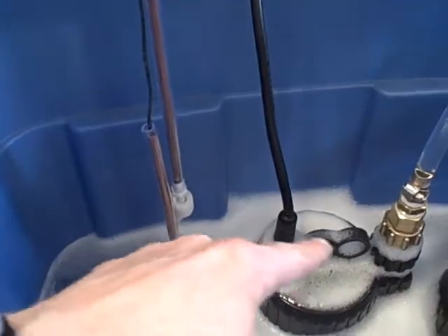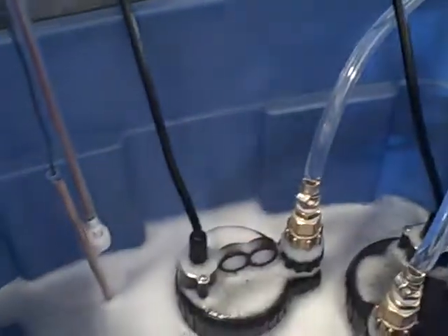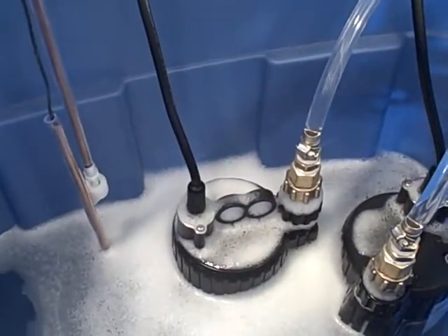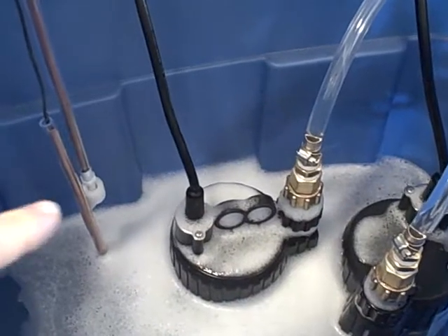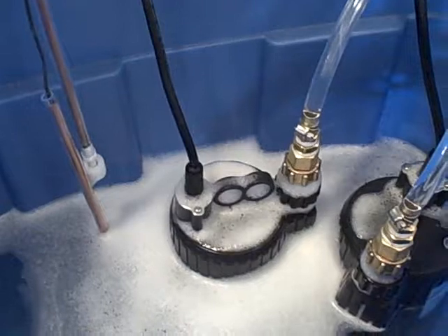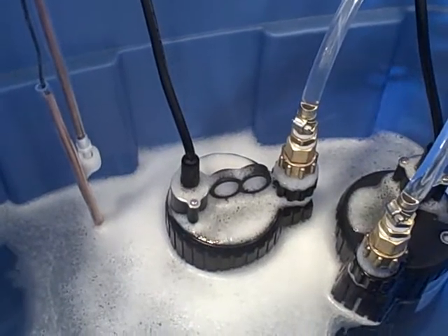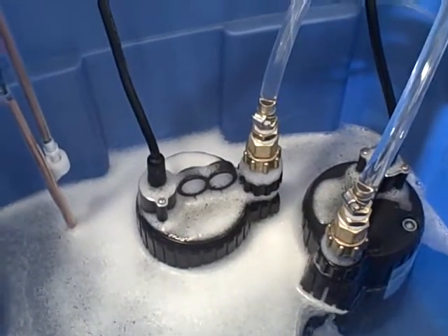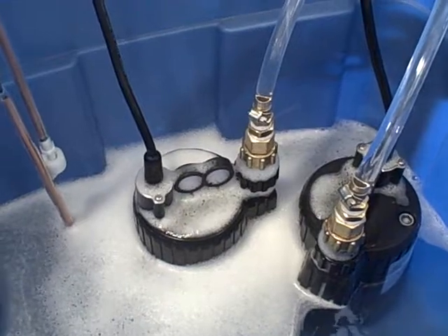When the wastewater reaches the high level switch, it turns on a pump, and that pump then pumps to the wastewater treatment plant. The pump continues to run until the wastewater gets down to the low level switch, at which point the pump turns off. Now, just like a normal wastewater system lift station, we have 2 pumps. We have one redundant to the other.